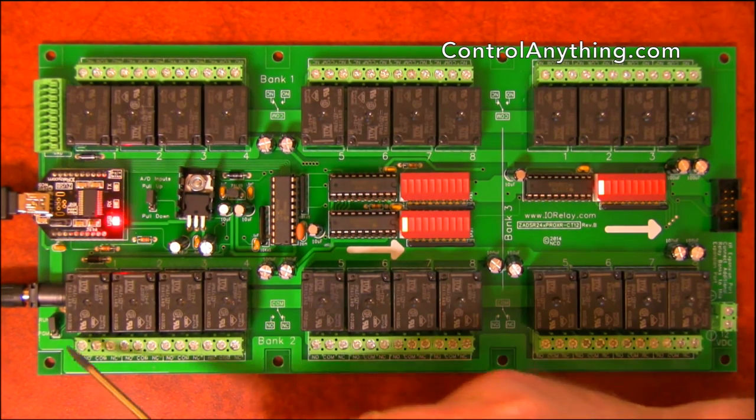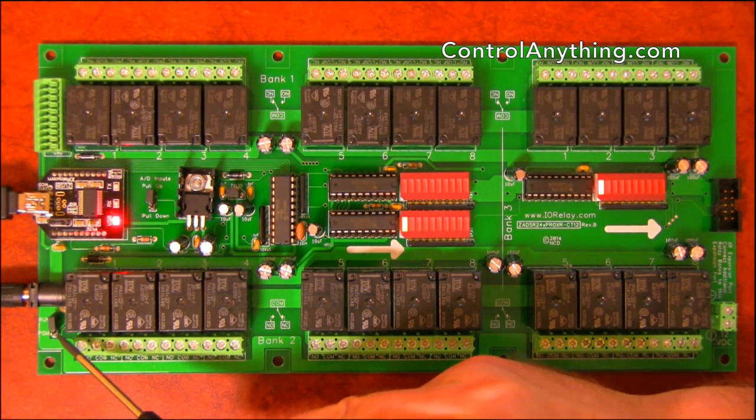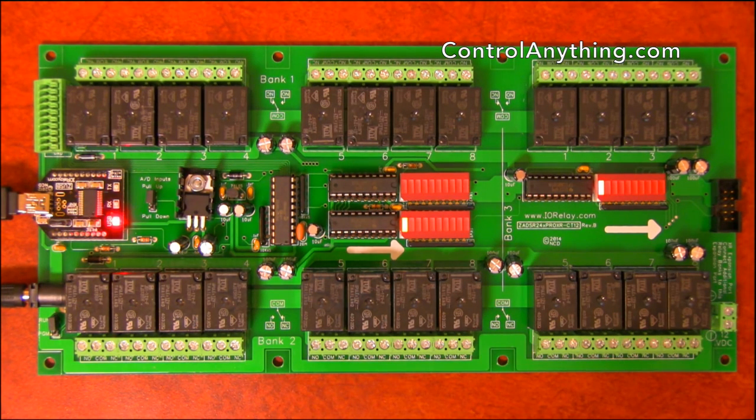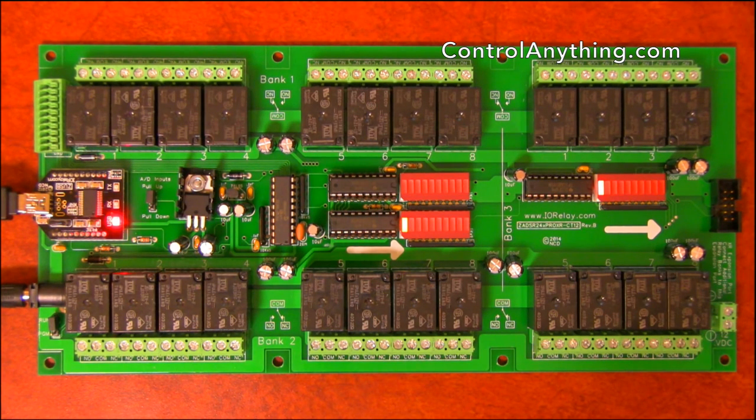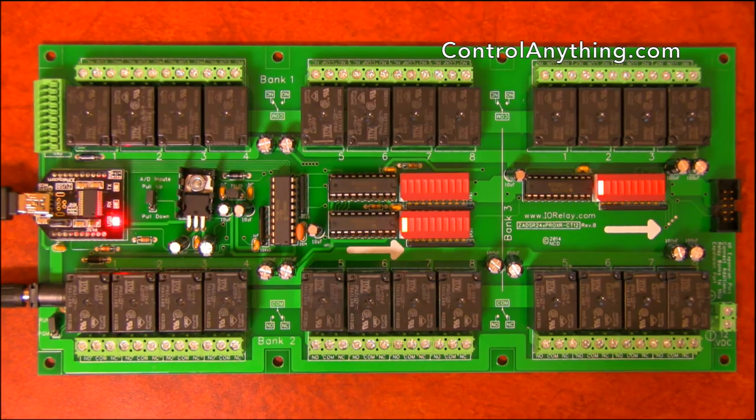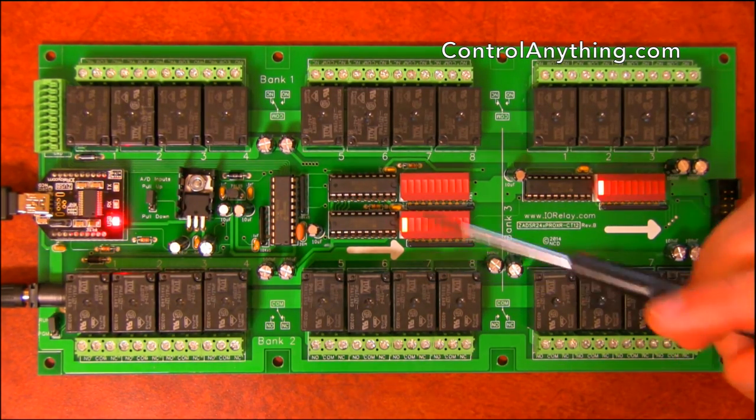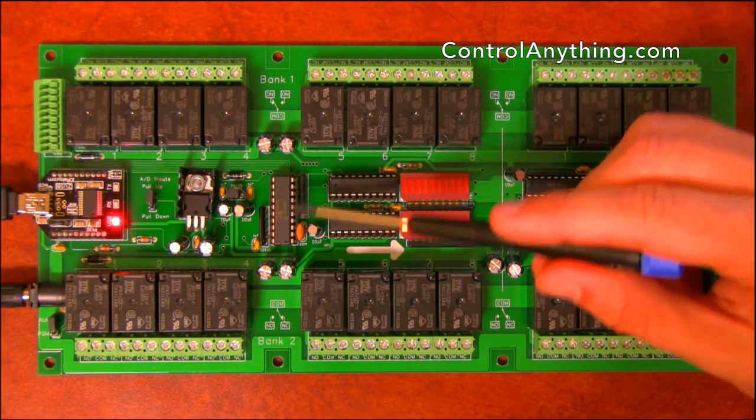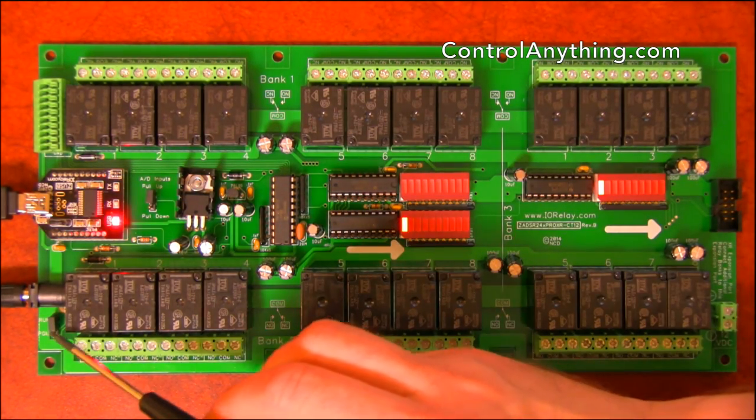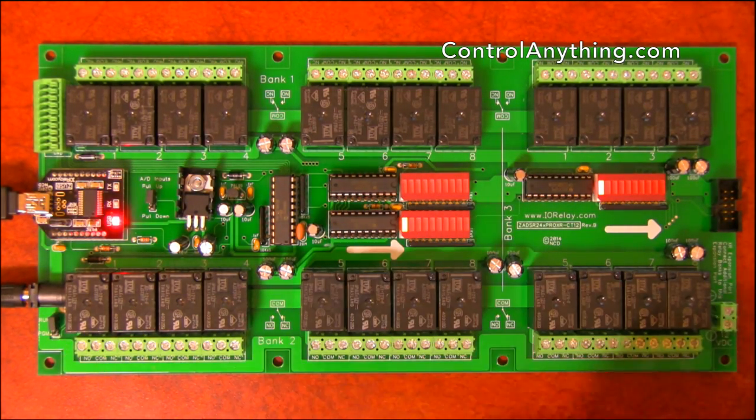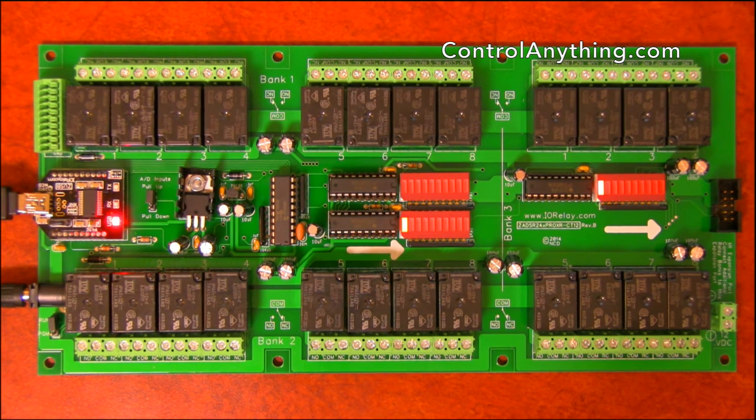And there's also an up down or a program run jumper. The program run jumper is used to recover these settings. Normally it's in run mode, but if you ever do get the settings a little bit misconfigured in this controller, you can always recover your settings by putting the controller into program mode and then running base station and that will allow you access to the features of this processor.